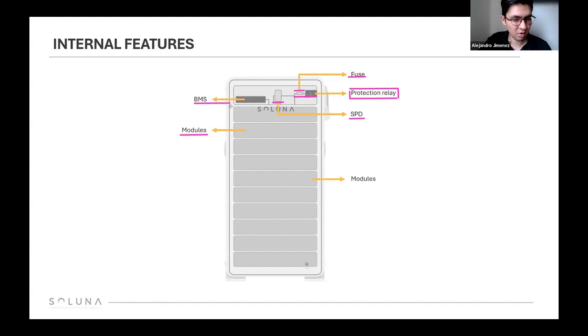Below the electric box, we have the modules. The 15K has 10 modules, and the 10K has 7 modules. Each module has lithium cells connected in series and parallel, and each module has a slave board. A slave board is an electronic board on this side. So all modules are connected and have communication. This is very important for the BMS because the BMS reads the parameters of each module. This is very important to mention because it's related to security. Also, each module has 2 temperature sensors. So the BMS is testing every module with the slave board and the 2 sensors to check the parameters.